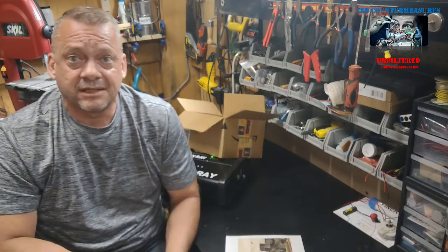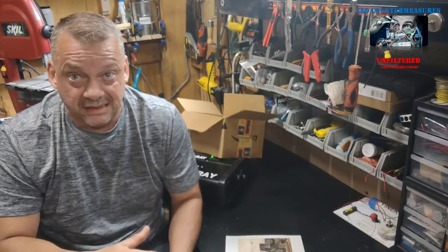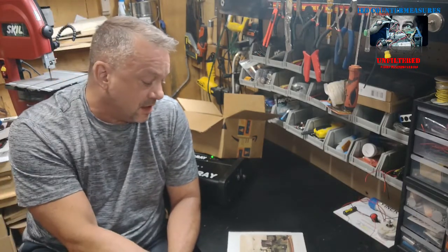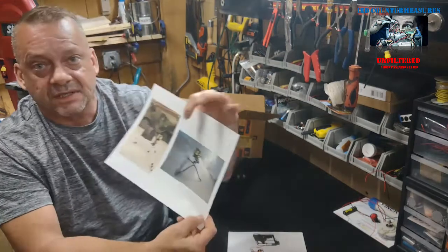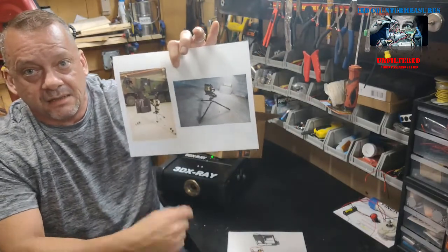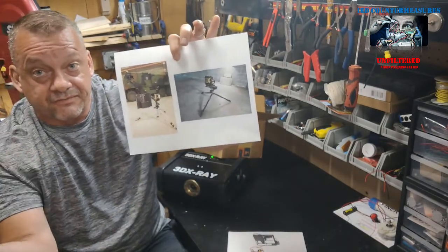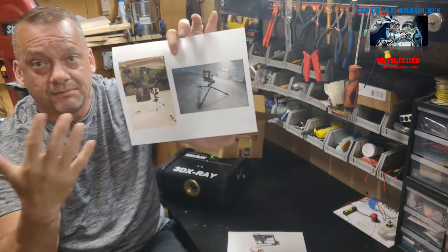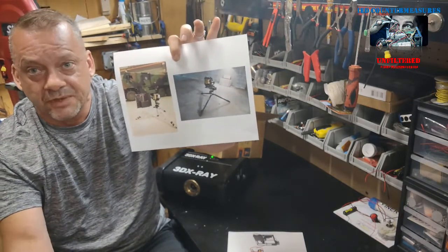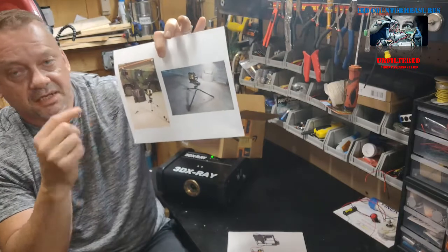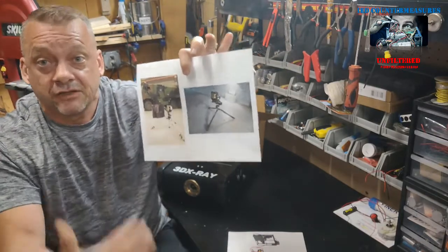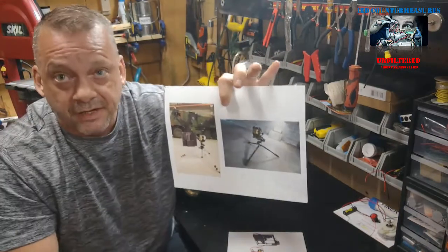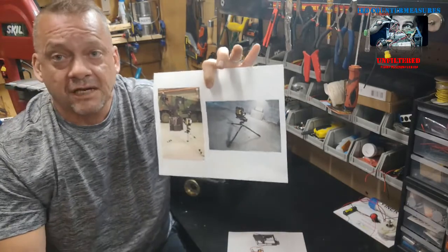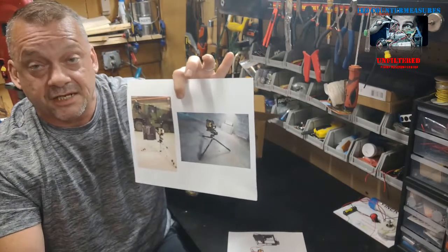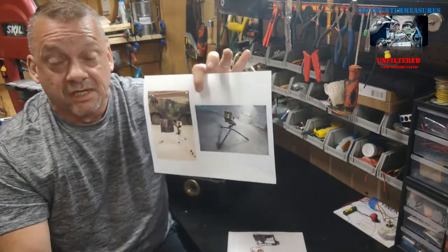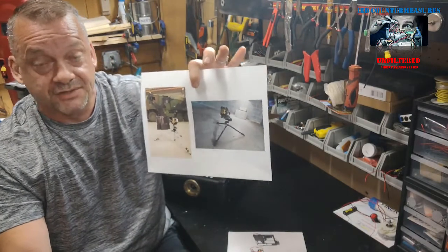There are other things out there that can significantly reduce lower edge dead zone - and here's one where they're using the generator on a tripod. This is just stupid, no reason for it whatsoever. If what you're X-raying is on the ground, your generator needs to be on the ground. If you're not doing that, you don't understand X-ray, and whoever trained you on this did a bad job.